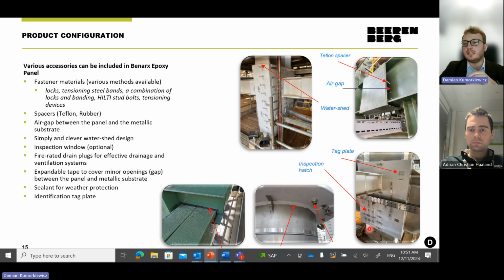We can design optional inspection hatches, so the project might have access to the relevant components, or to check the corrosion conditions of the metallic substrate, or check water accumulations. Then you have fire-rated drain plugs, which drain water out from the system, and you have a weather protection silicone-based sealant just to prevent water ingress through small gaps between the panel and metallic substrate.